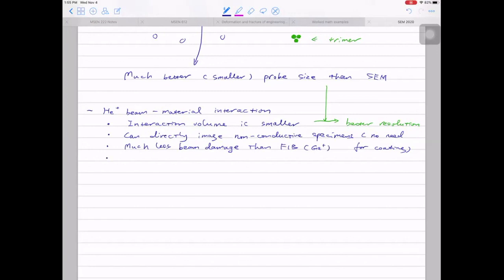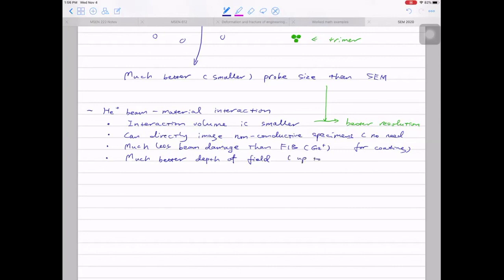Another advantage — in most cases due to the optics design — is that you have a much better depth of field. This means even if you have super non-flat features, you can have everything in focus. By playing with working distance in regular SEM you can change the depth of field, but in helium ion microscopy the depth of field is dramatically improved — it can be up to 1.5 millimeters, which is remarkable.